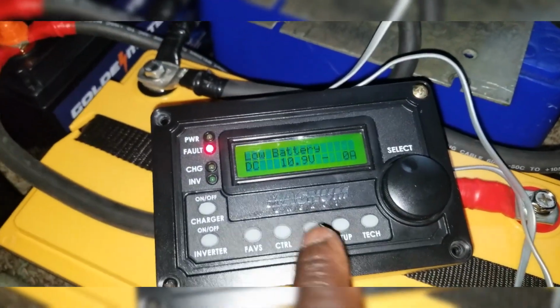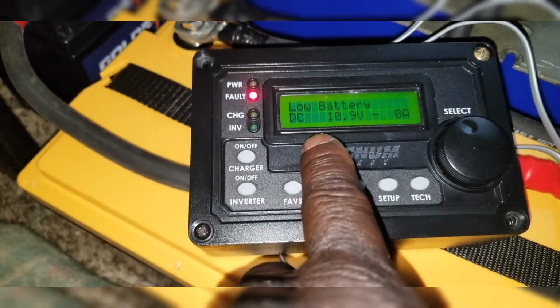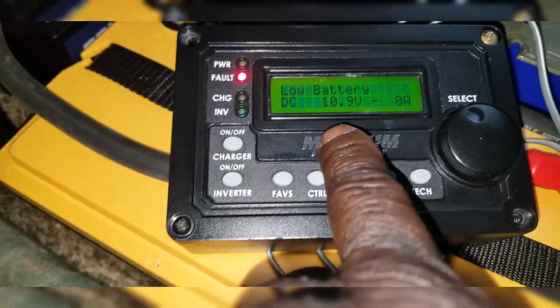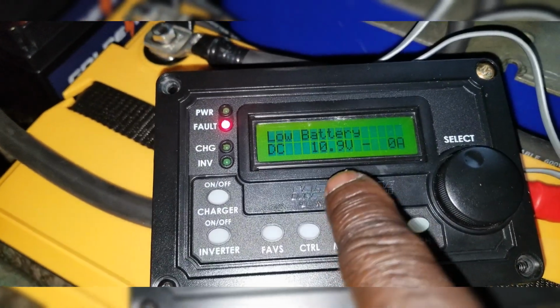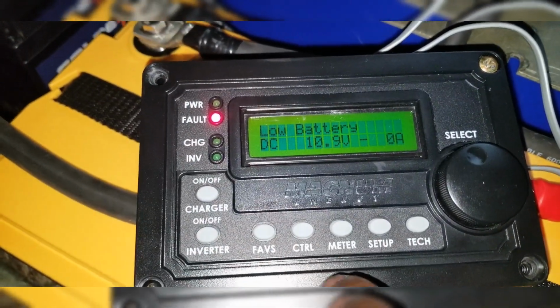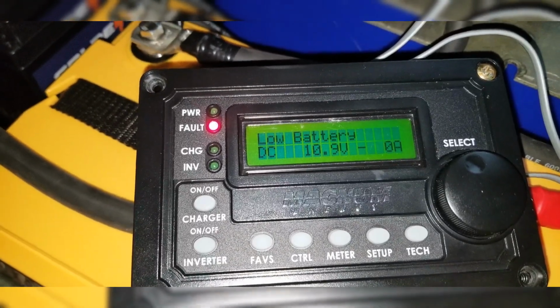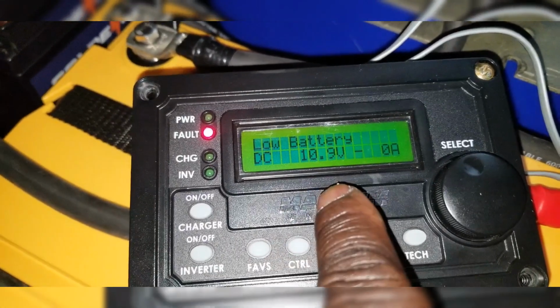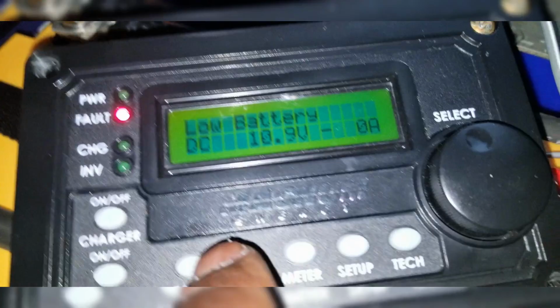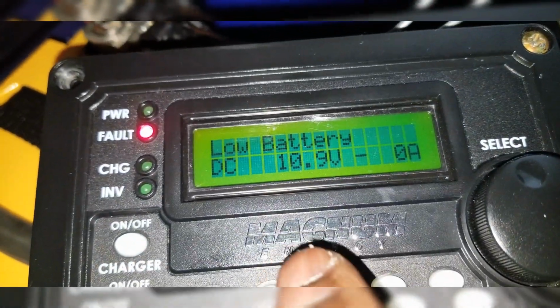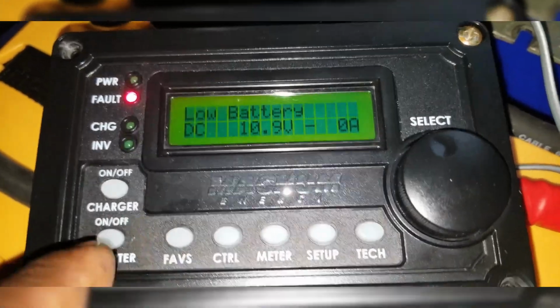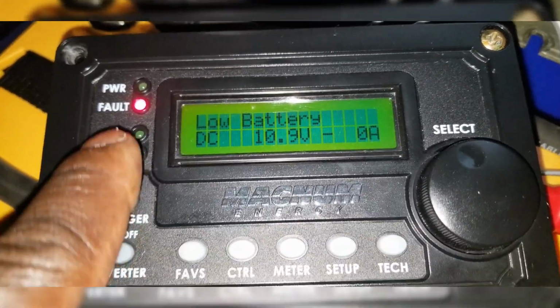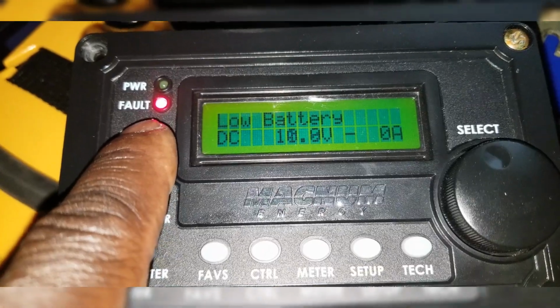It's not the BMS. If the BMS had shut off on the inverters, there would not be any power left. But the inverter shut off, I saw it shut off at that point. If I had gone below 9 volts, or 9 point something, or 8 volts, then the BMS would shut down completely and there would be no incoming power here. So the screen is lit, okay, it's green. That's because of the light on the camera that you still have this light. Otherwise the BMS would have shut down completely.